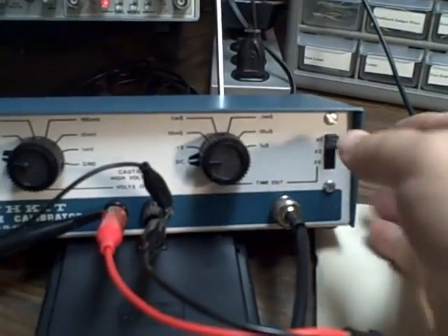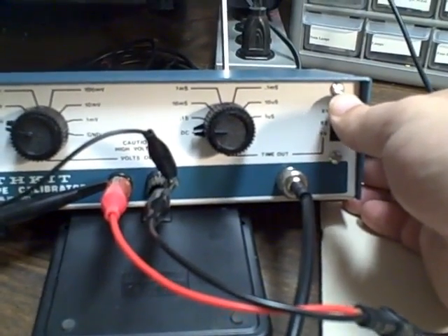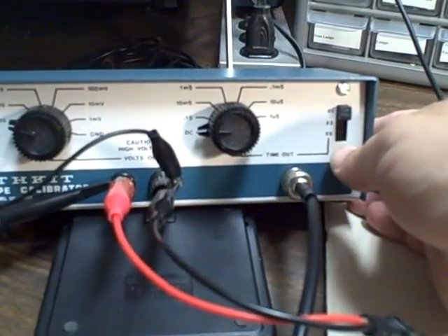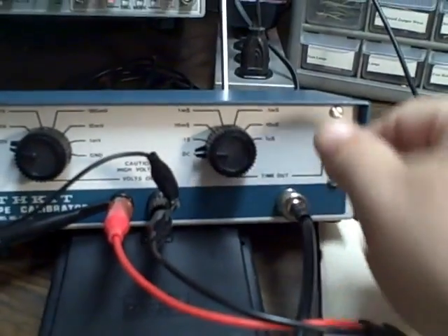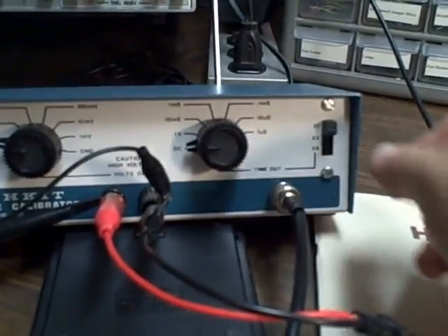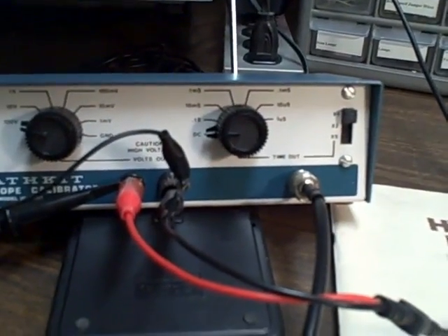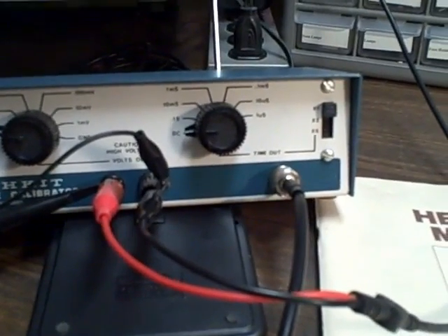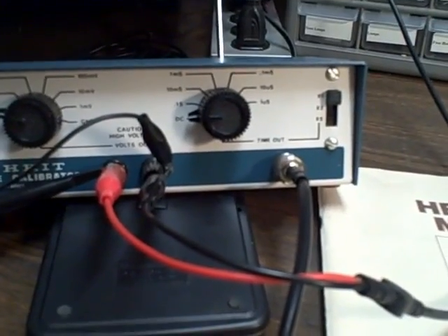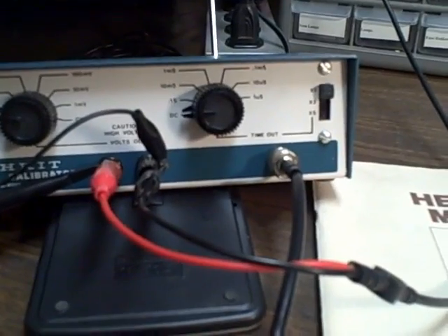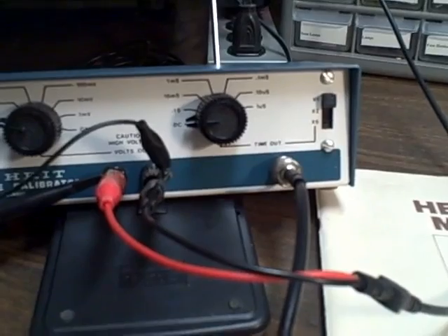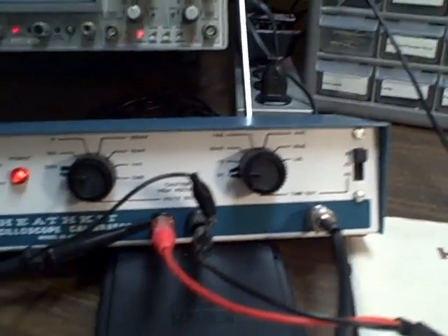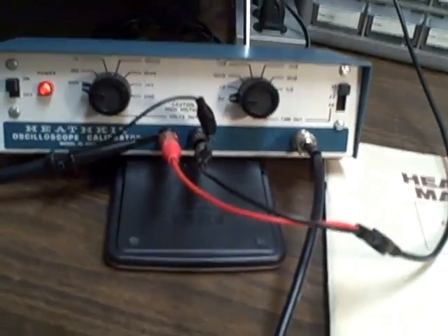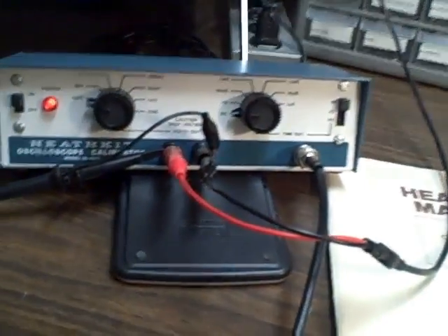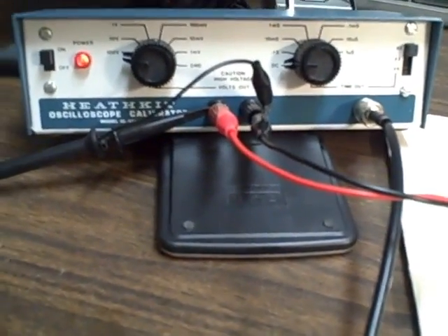and it'll do that in 6 ranges, but then it extends those ranges by allowing you to divide each range by 2 or by 5. So basically you're multiplying your range setting by whatever the switch setting is. If I was at 0.1 seconds and I go to the times 2 position, I now am going to have a 0.2 second waveform period, which means I'm going to cut the frequency in half and double the period. So that effectively gives you 18 different ranges that you can work with in frequency. On top of that, you can provide various voltages out at those frequencies as well, and we'll give you a demonstration of that.